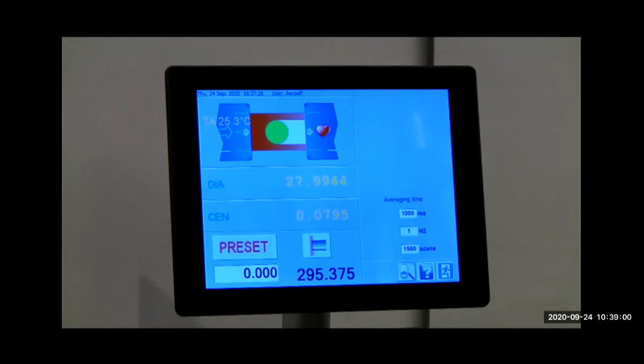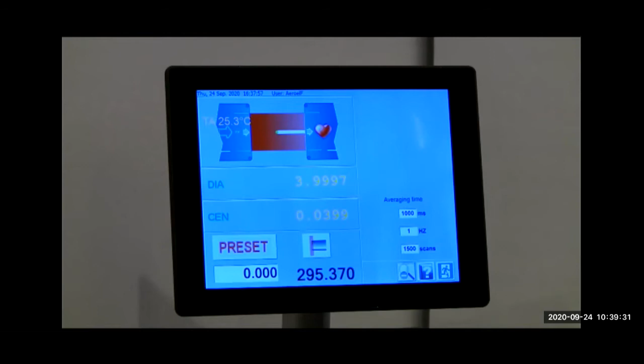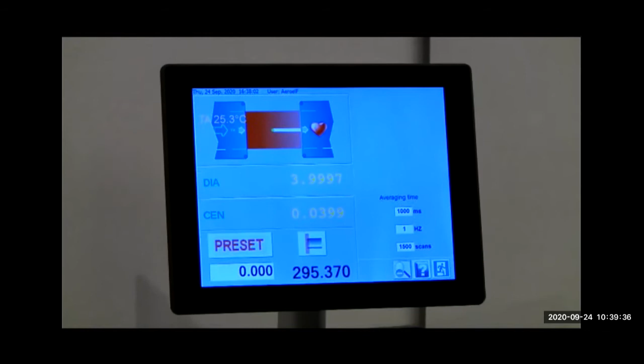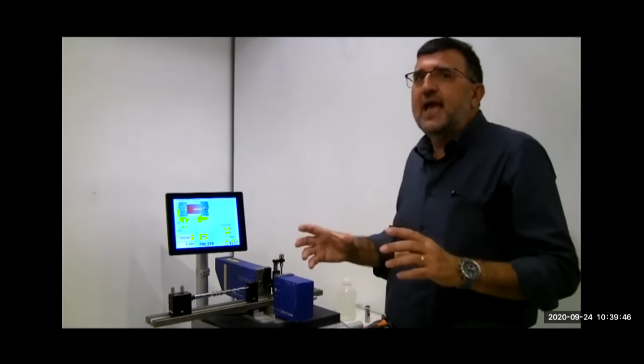We give in our datasheet 3 types of linearity error. The linearity error is the difference between the value that you read and the real value of the diameter, because all types of masters have a nominal value, but also an error. If I check the certificate that the metrology laboratory gives me for a master, it gives me a value, but also an error. So the linearity is the difference that we can have between the system calibrated in Italy in our laboratory and the value of the diameter of the products all over the world.